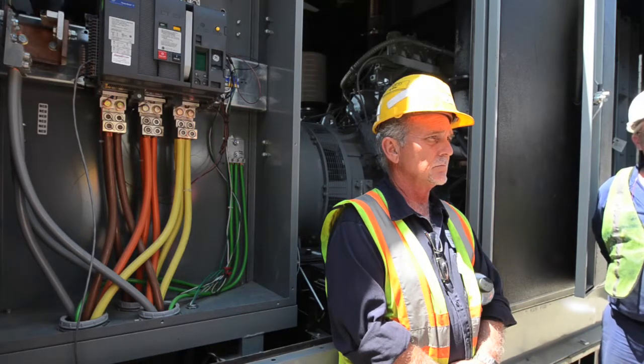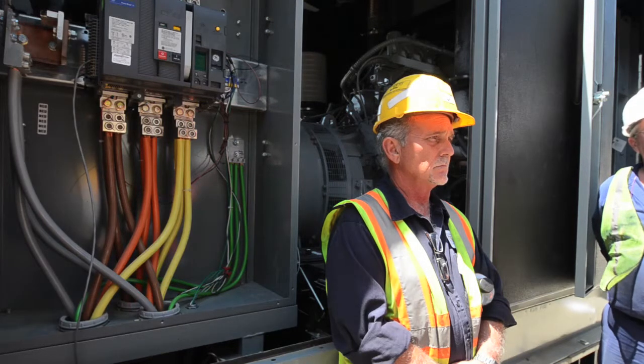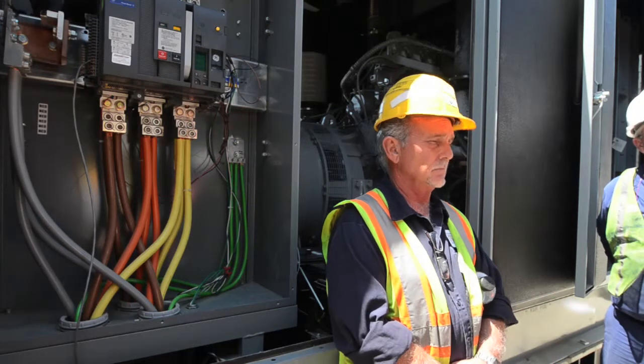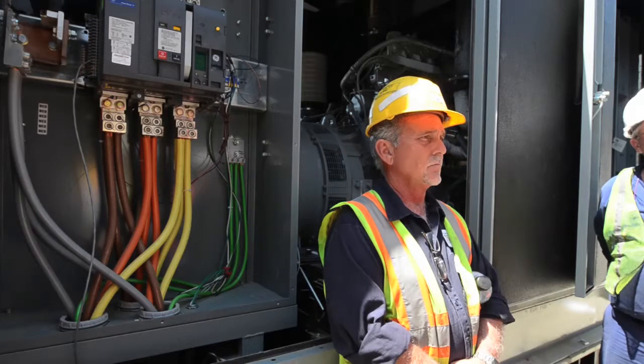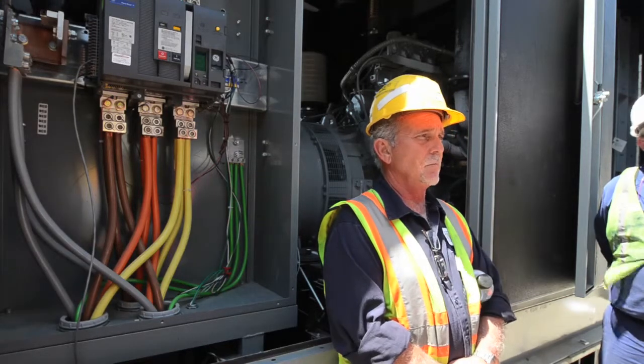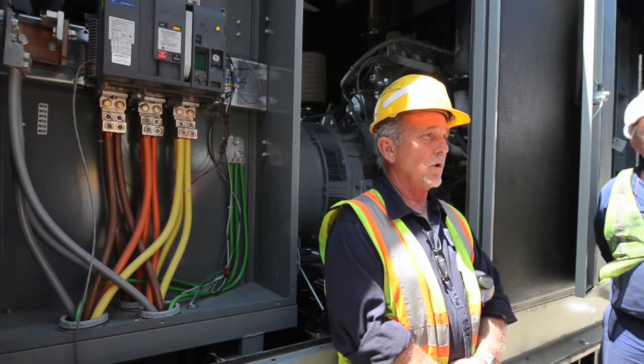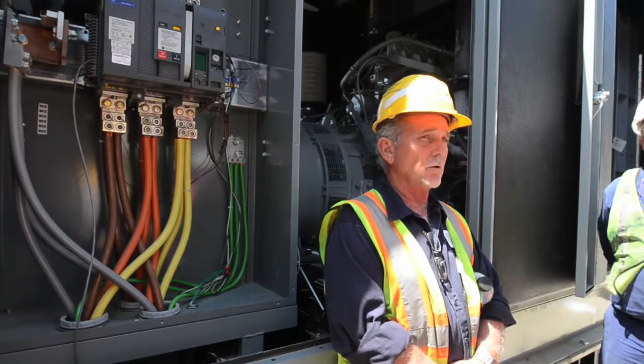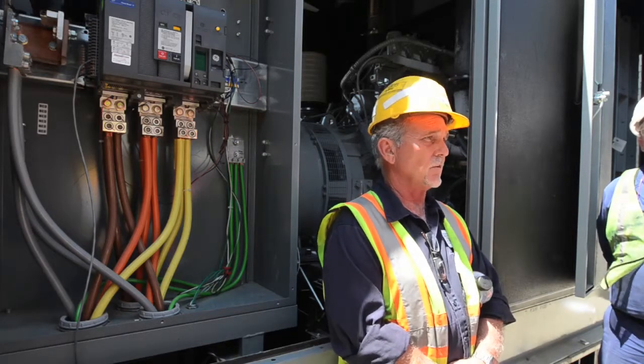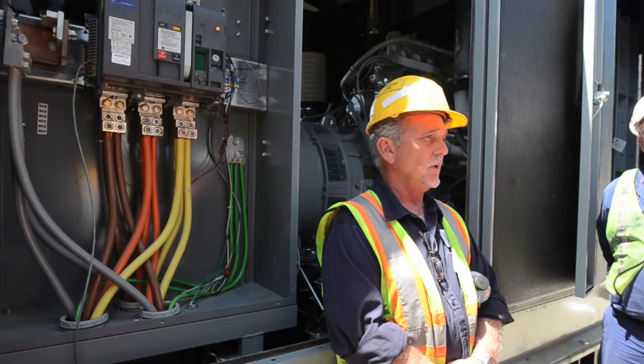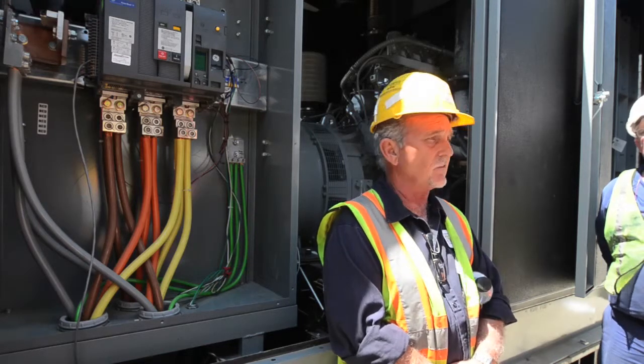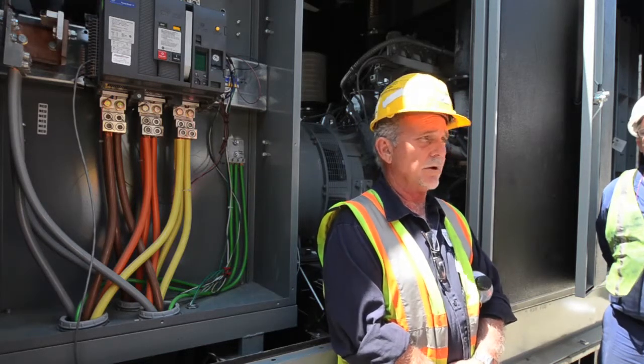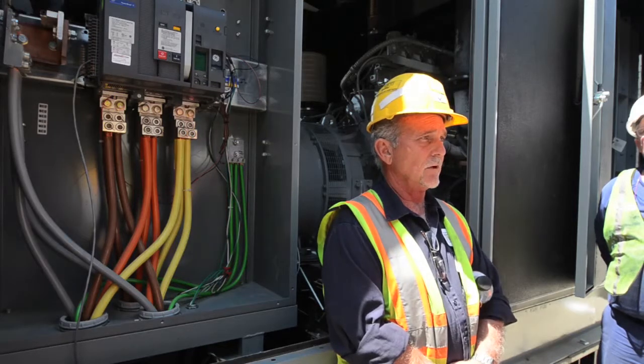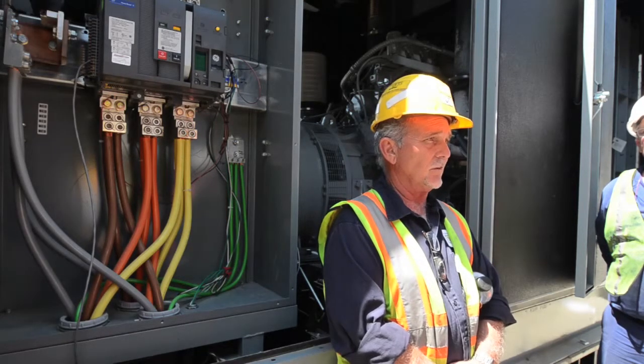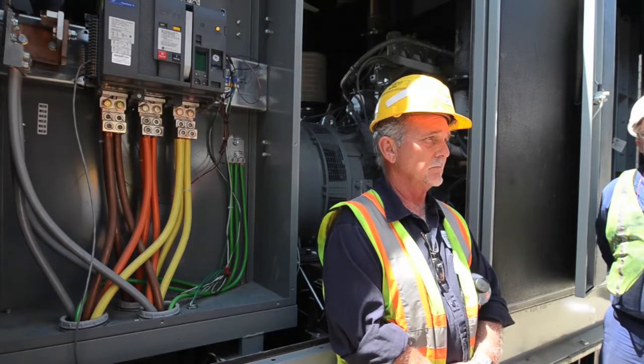Considering our position here, we're normally doing the regular weekly checks. You can run it, but you can't load it. What you can do is go downstairs and run them both off the ATS, do the test on the ATS. If you configure the ATS that way, you can start both generators and just run them. But they're not going to close to the bus unless you allow for a transfer.